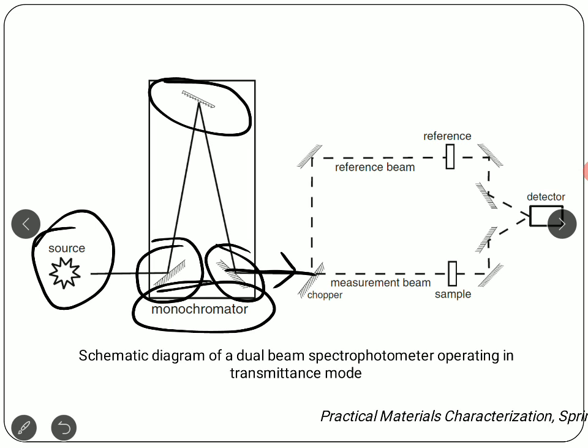Next we have a chopper. Even without the sample, other components like mirrors and the monochromator can create additional signals not coming from the sample. So we chop the signal — dividing it into two parts. One part goes to a reference, which might be an empty cuvette or sample holder. The sample beam includes contributions from the cuvette, and both signals are fed into the detector.